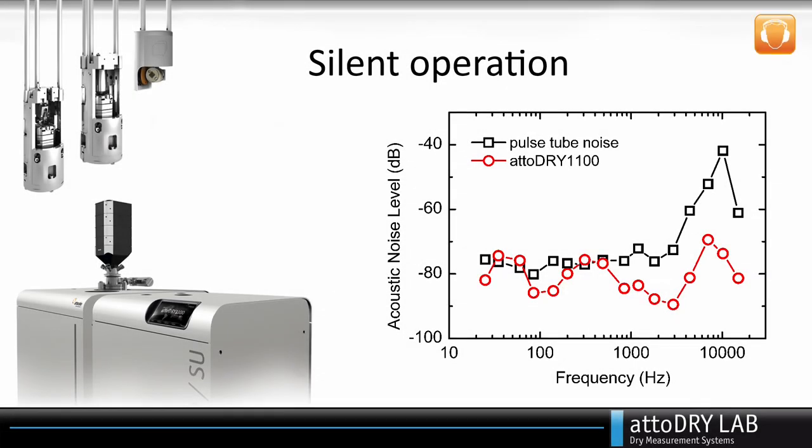Last but not least, special care was taken to reduce the acoustic noise of the inherently loud pulse tube cooler by more than 90% at the most relevant frequencies.